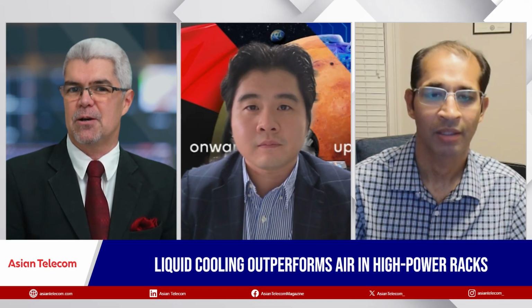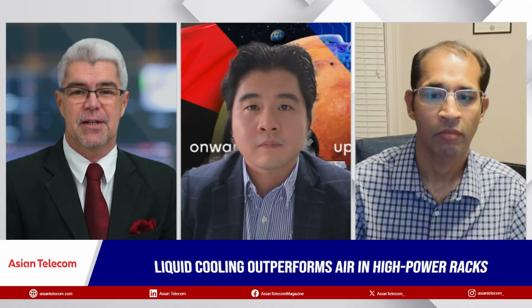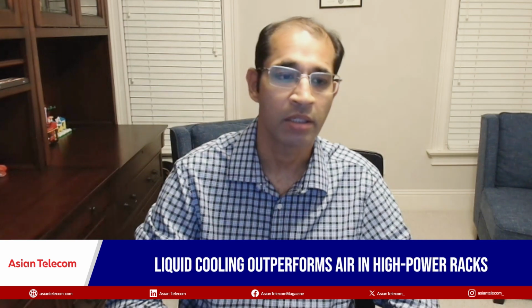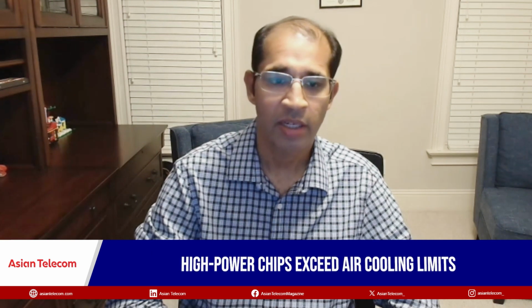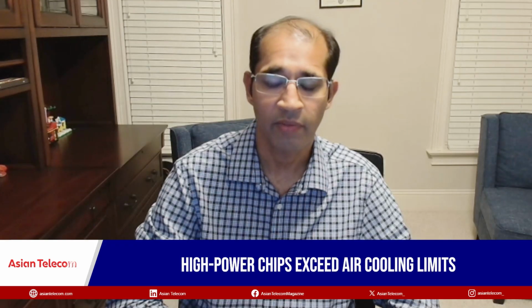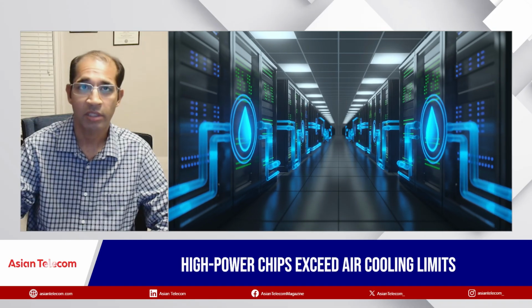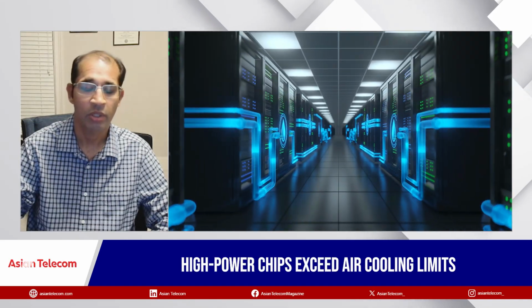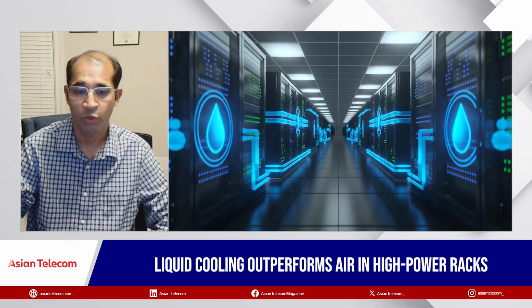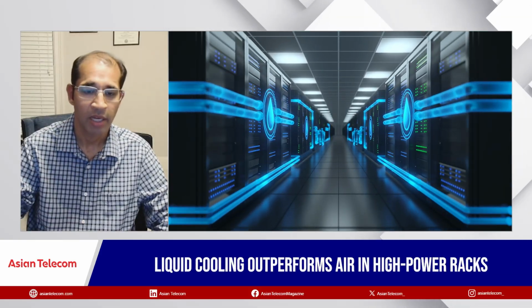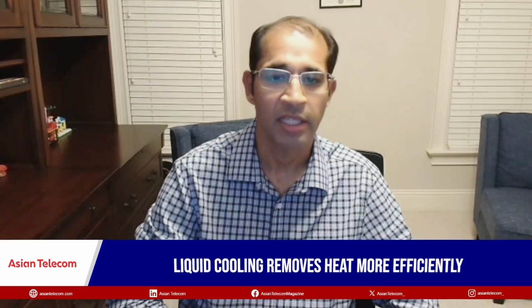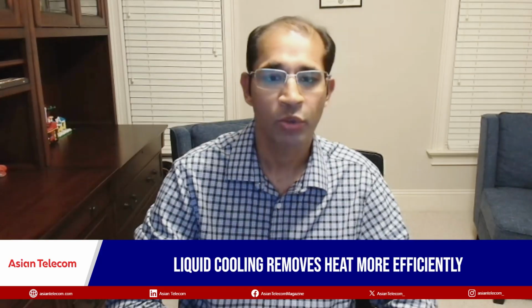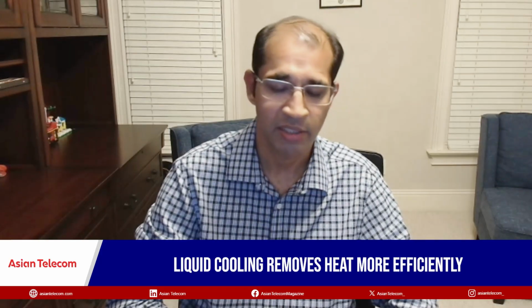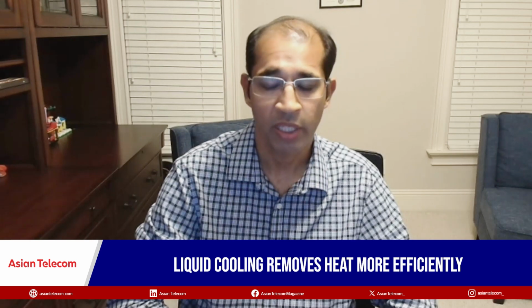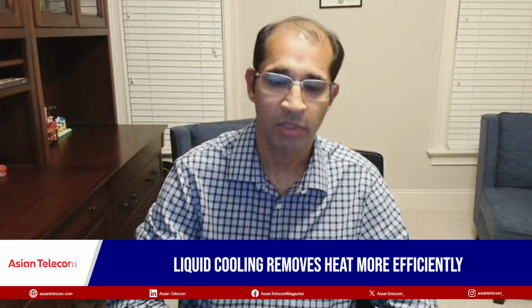Why is liquid cooling more effective than advanced air cooling? With increasing compute demand, new chips and server racks have higher power requirements, and current air cooling is no longer effective at taking the heat away. Liquid has much higher specific heat capacity and higher thermal conductivity, so it's better at removing heat from high-end servers and chips. That's why there is a move from air cooling towards liquid cooling, with other advantages including improved PUE, reduced cost, and much higher compute density.